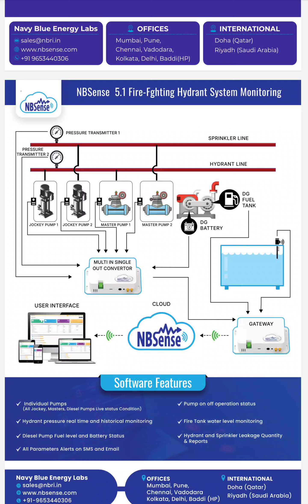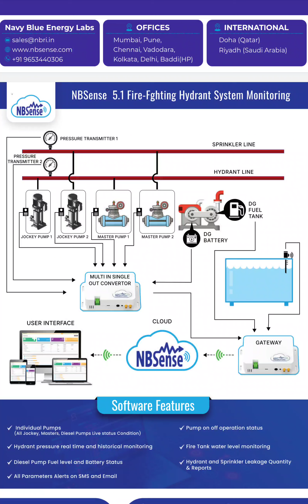Then we have the firefighting hydrant system monitoring. Health monitoring of the entire building's firefighting hydrant systems, or of all its components, is possible on our dashboard. There are different types of components. Majorly there are two separate lines, the sprinkler line and the hydrant line. Sometimes they are separate systems, sometimes not. It is a standard installation. They have the jockey pump and master pump, mostly electrically driven, and the emergency pump, which we call the diesel pump. Whichever health parameters of these components, the jockey pump, master pump, hydrant pressure and sprinkler line pressure, we can monitor through our dashboard.